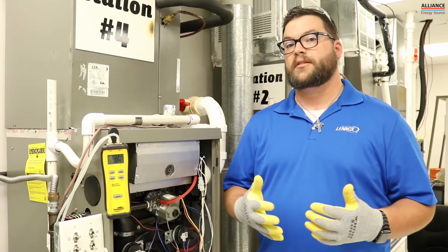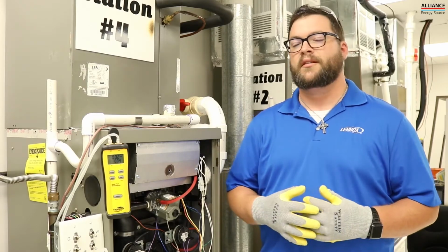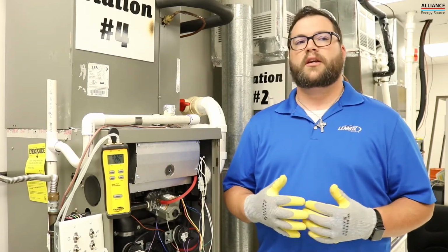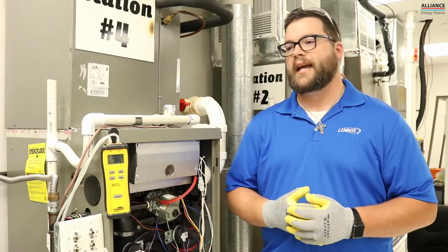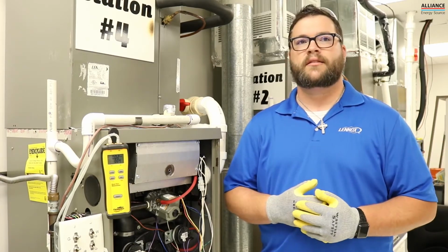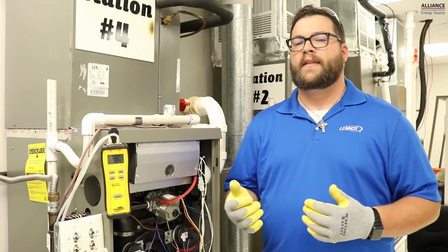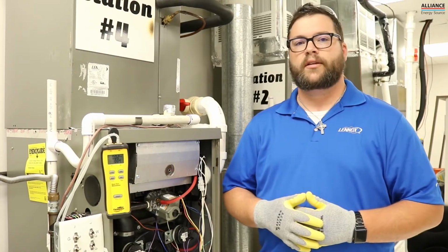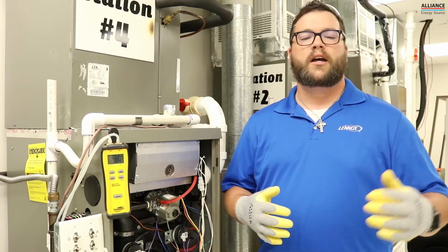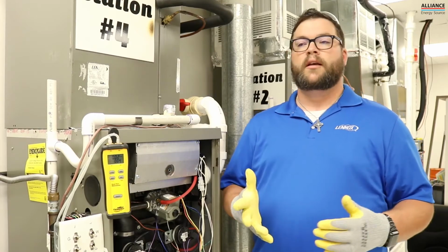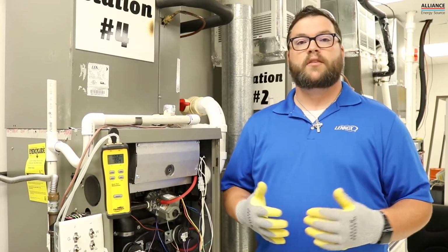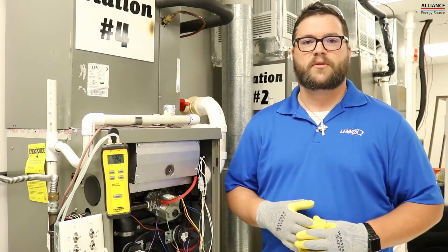When you come to a system for a no-cool situation, it's pretty common for the technician to want to go out to the compressor and say, hey, yep, the compressor is overheated, and that's because the evaporator coil is dirty, so you just need to clean your evaporator coil, or maybe to the extreme of you need to replace your compressor because that's what's going on.